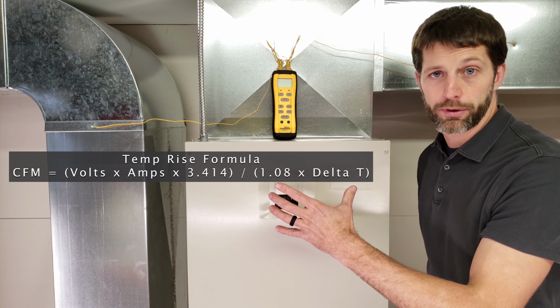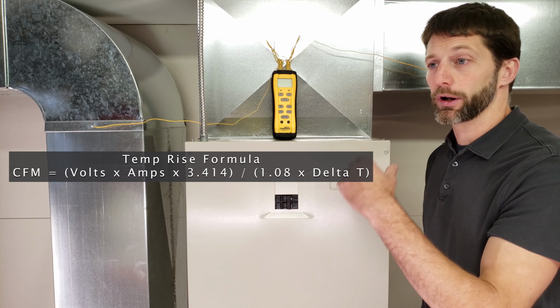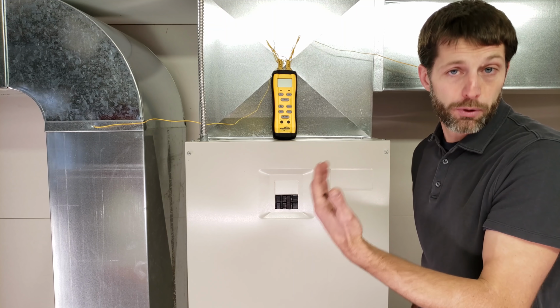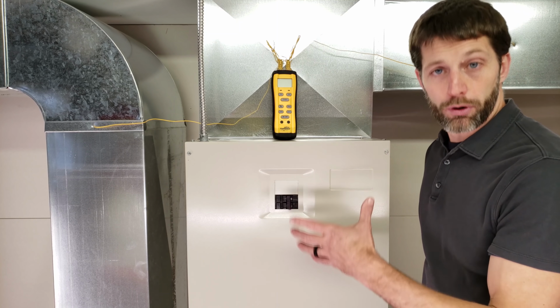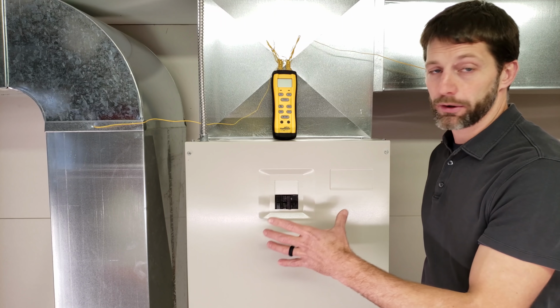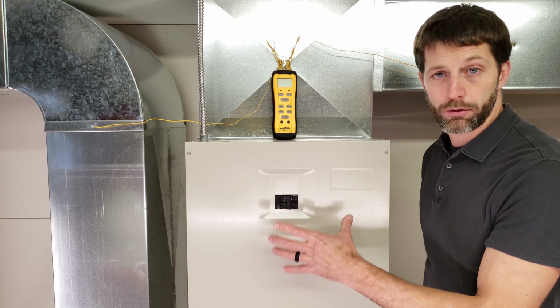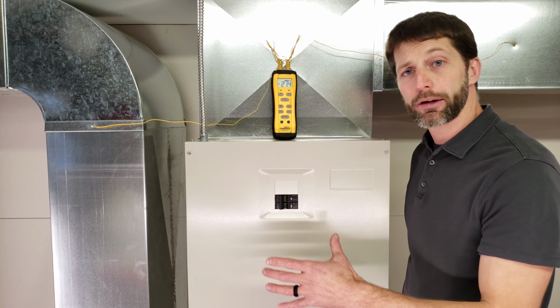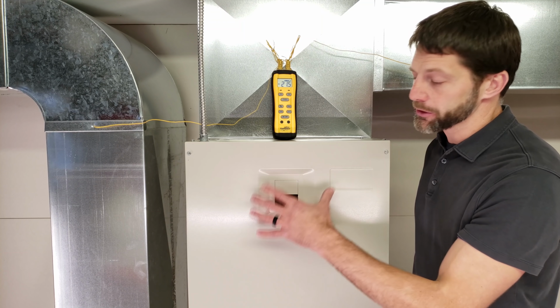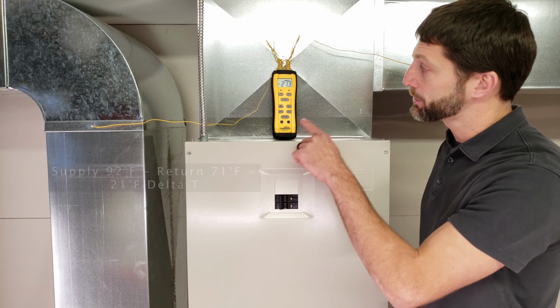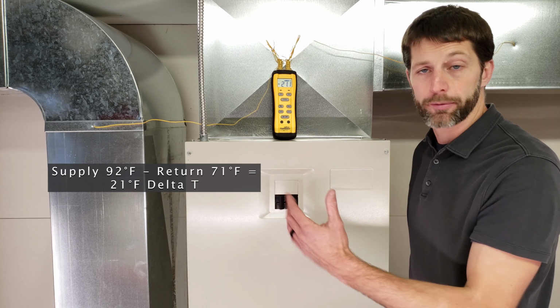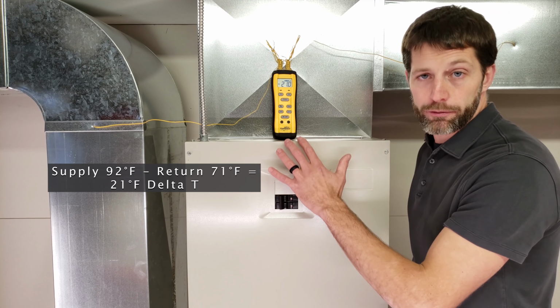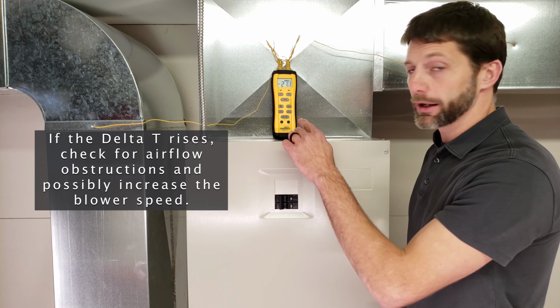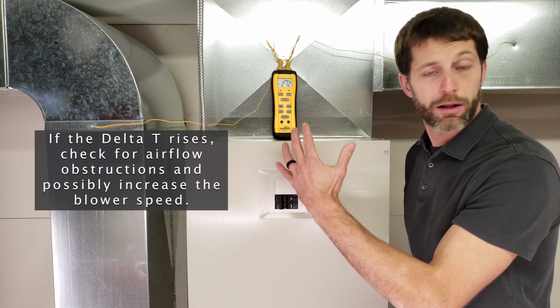You can actually do the same thing for a gas furnace or a fuel oil-fired furnace, in order to determine the actual airflow. Now we're going to go ahead and get into our air handler, and we're going to turn this air handler on, but we're going to be turning only the electric strip heating on and not the heat pump. So now we have our air handler running in heating mode with just the electric strip heating, and we see that we have a delta T of 21 degrees roughly. So that should be remaining fairly steady. It should not continue to rise. It should just be at that same level the whole time.